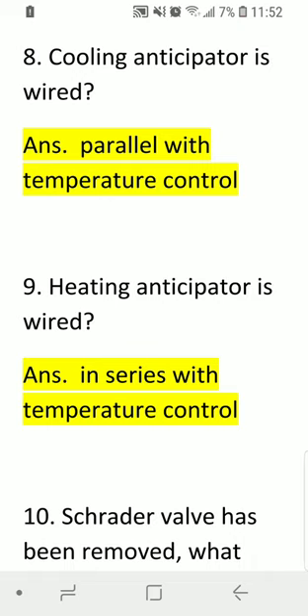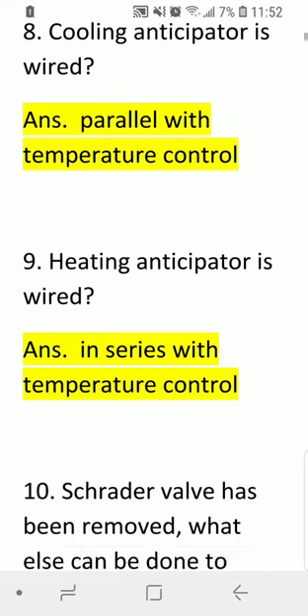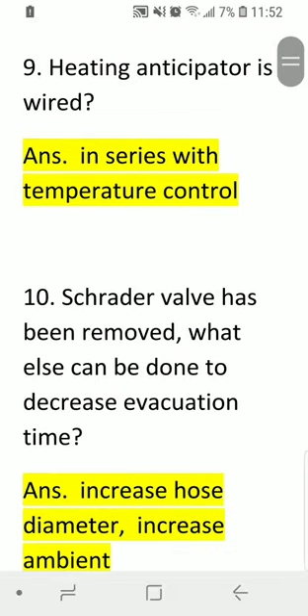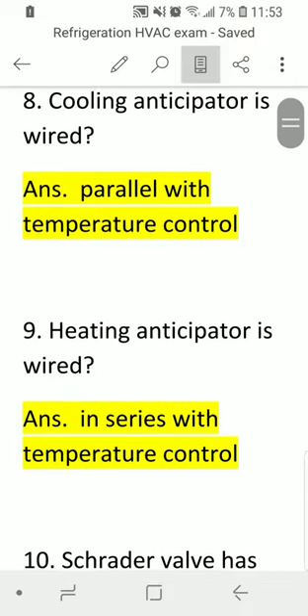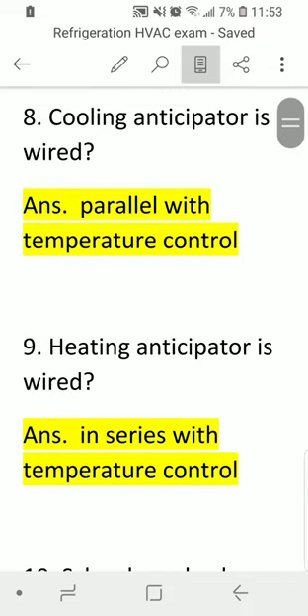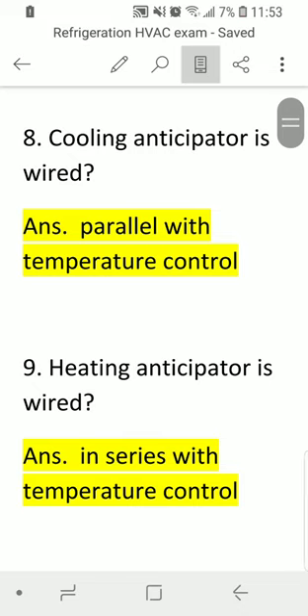Question eight: how is a cooling anticipator wired? Answer: in parallel with the temperature control. Question nine: how is a heating anticipator wired? Answer: in series with the temperature control. So the cooling anticipator is wired in parallel while the heating anticipator is wired in series with the temperature control.